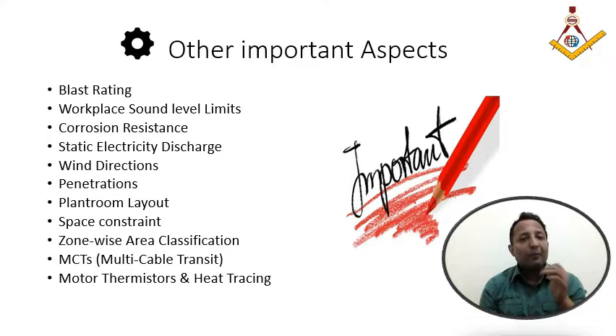There are very few equipment or damper manufacturers who produce blast rated dampers. Normally the length of those dampers is almost 1 meter, so that they can mount all the arrangements, and there's a spring that can sense the sound pressure and closes automatically after achieving that pressure. This is what the dampers are made up of.